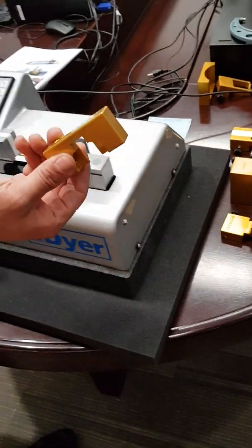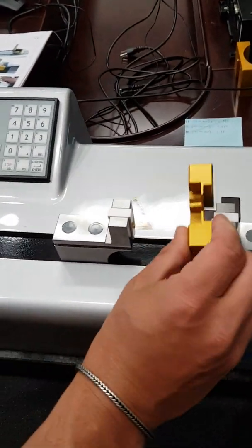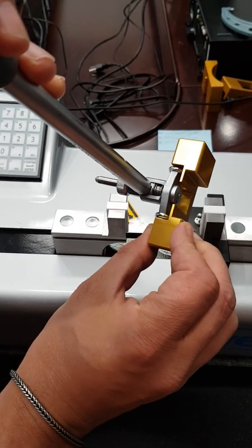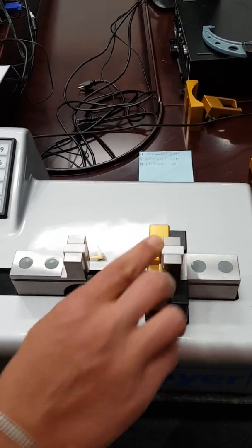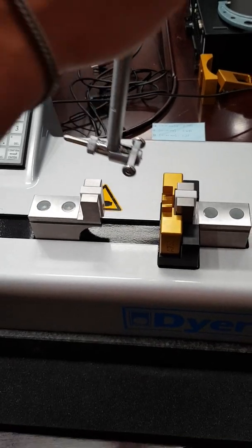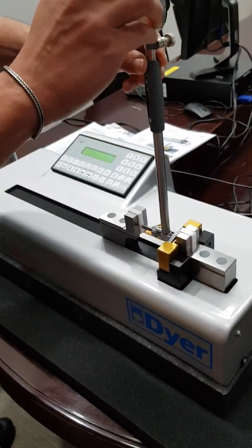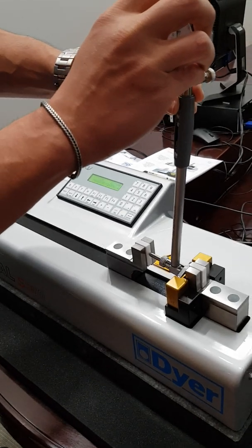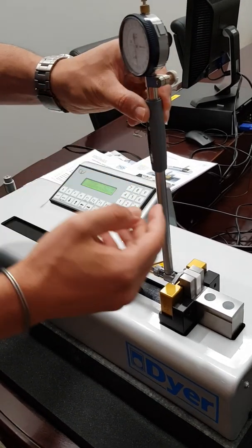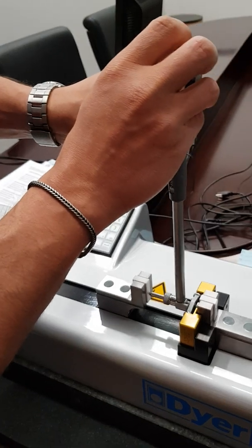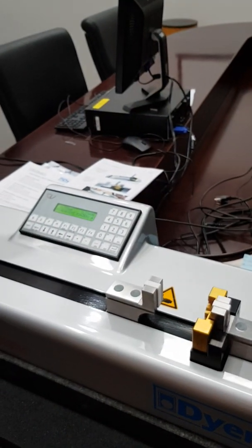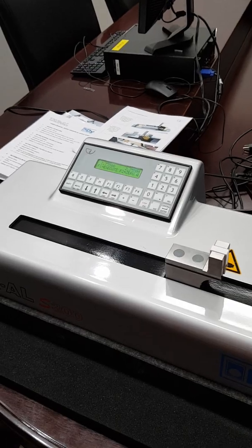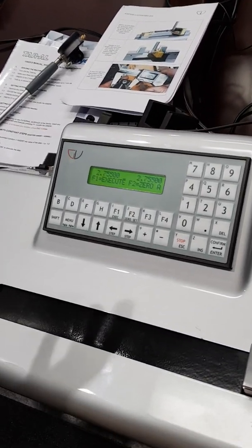Now we have to locate the right adapter. This is the right adapter for this bore gauge. We lock it and we're ready for the zeroing. This way the instrument is moving only on one axis and I find the reversal point very easily. So in a few seconds my bore gauge is set to zero.